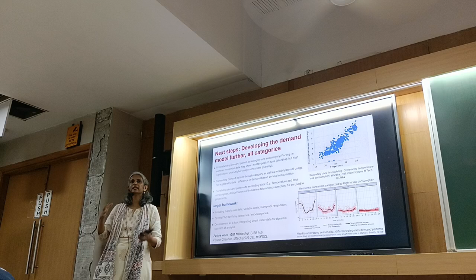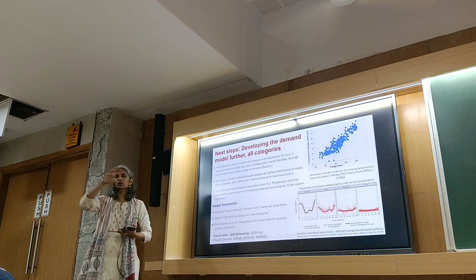Eventually this will also be used for supply side planning - how much solar can be integrated into the grid without it becoming economically problematic. So it's supply side as well as demand side, and really the transmission system is also a factor in all this, because depending on where the plants are and where the demand is coming from, the transmission system needs to be planned.